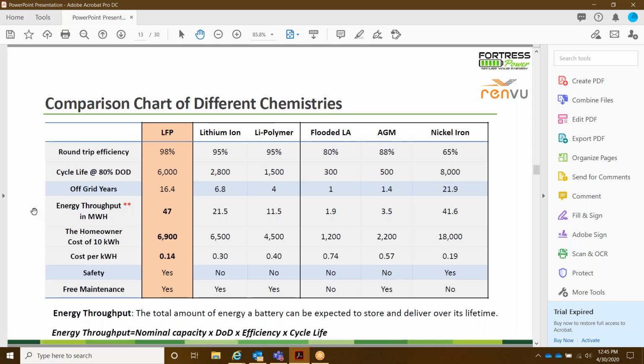Also want to point out the energy throughput in megawatt hours of lithium iron phosphate chemistry. Energy throughput is the total amount of energy a battery can be expected to store and deliver over its lifetime. You can calculate it by taking the nominal capacity multiplied by the depth of discharge, multiplied by efficiency, multiplied by the cycle life.